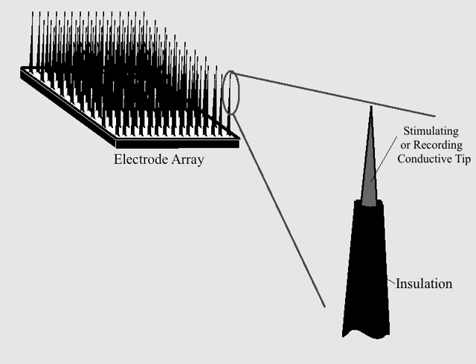Electrical impedance is the opposition to current flow with an applied voltage, usually represented as Z in units of ohms. The impedance of an electrode is especially important as it is directly related to its effectiveness. A high impedance causes poor charge transfer and thus poor electrode performance for either stimulating or recording the neural tissue. Electrode impedance is related to surface area at the interface between the electrode and the tissue. At electrode sites, the total impedance is controlled by the double layer capacitance, which is directly related to the surface area. Increasing the surface area at the electrode-tissue interface will increase the capacitance and thus decrease the impedance.